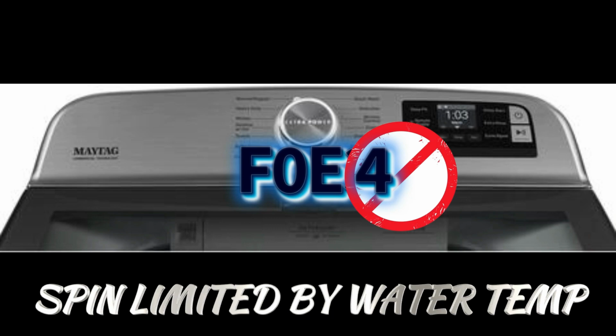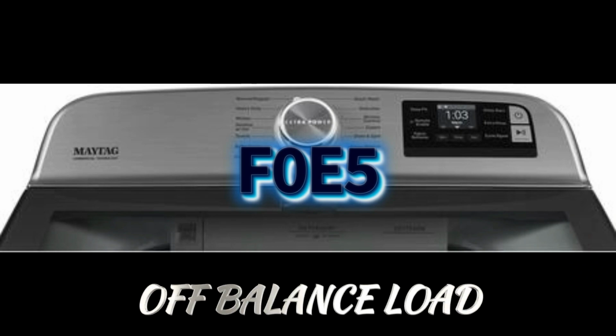F0E4. If you get this code, it could be caused by a cold environment, cold water supply, faulty water thermistor, or your main control board. Error code F0E5 could be caused by unbalanced load, overloading or underloading, or suspension rods. So these would be the things I would check out.